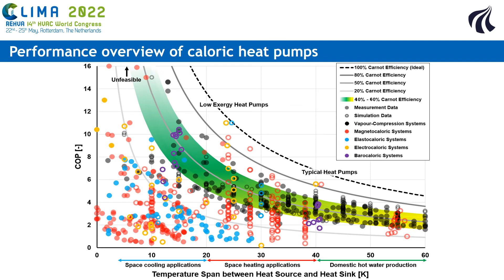The best electrocaloric heat pump prototypes show promising COPs of 9 to 14, but for temperature lift and effective power that is insufficient for building applications. However, theoretical studies suggest that an adequate temperature span for space heating and cooling can be reached with electrocaloric heat pumps. There is no available experimental data for barocaloric heat pumps, but simulation data suggests that such technology could sustain a 40 to 60% Carnot efficiency for temperature lifts up to 40 kelvins.